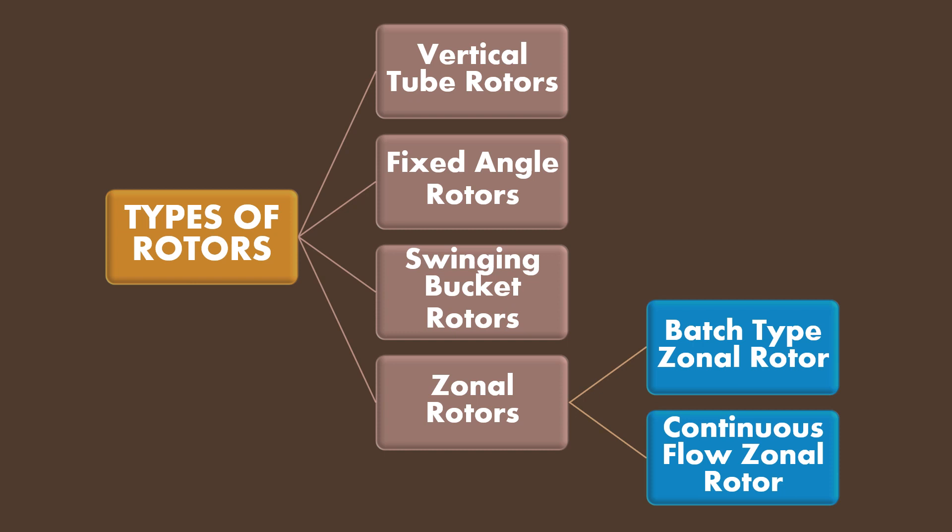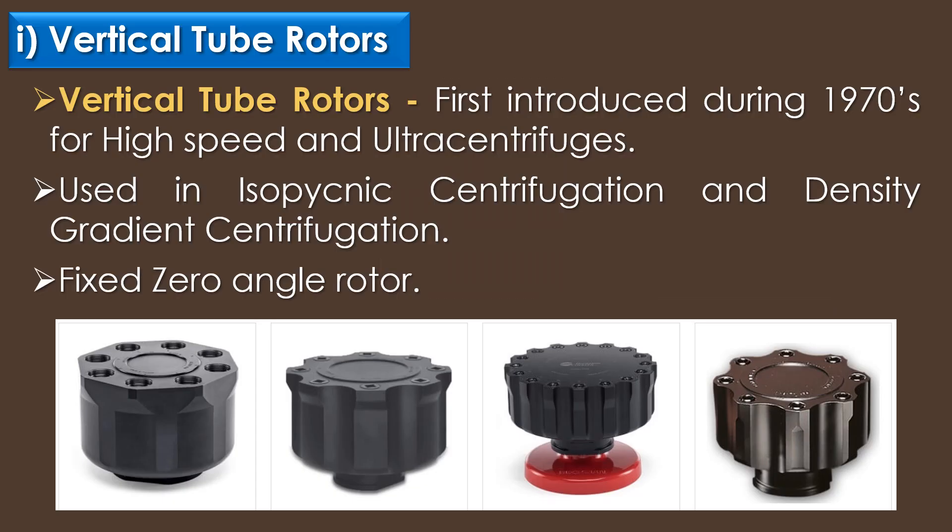The zonal rotors are further categorized into two types: batch type zonal rotor and continuous flow zonal rotor. The first type of rotor is vertical tube rotors. Vertical tube rotors were first introduced during the 1970s for high speed and ultra centrifuges. They are commonly used in isopycnic centrifugation and density gradient centrifugation. The vertical tube rotor is a fixed zero angle rotor.